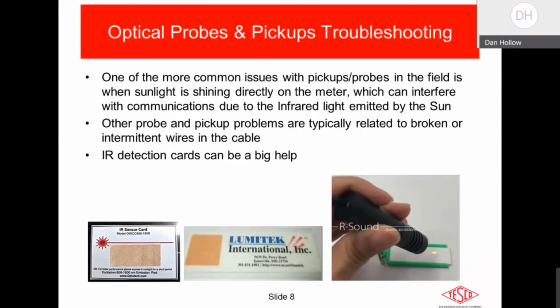So the first thing I would do in using one of these, and I did this many, many years ago when I was a test department supervisor running a production test department for a meter manufacturer, I would hook up my probe to the laptop, run the meter manufacturer software, and put that optical probe head over that card where that piece of yellow paper is. On the right, it's a white piece of paper that's treated with that chemical. Put the optical probe head over that card and then start the communication session on the vendor's software. You should see flashing. If you don't see flashing, then that means the infrared LED is not flashing and pulsing as it needs to.